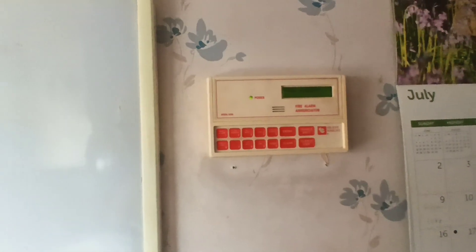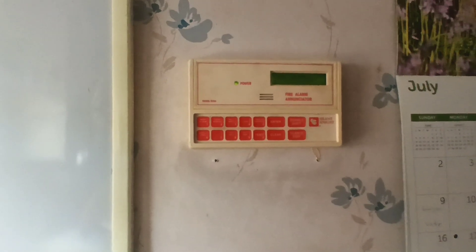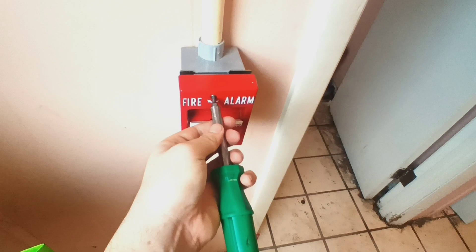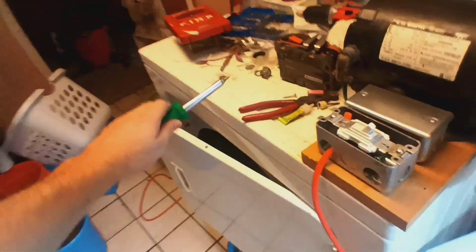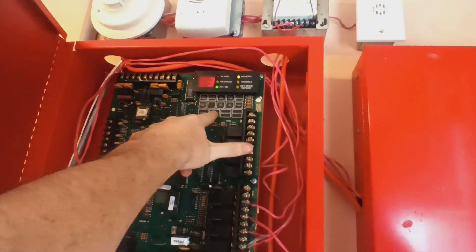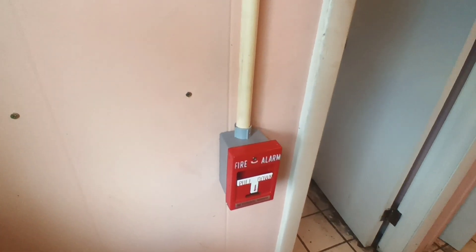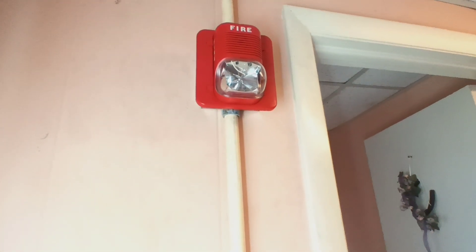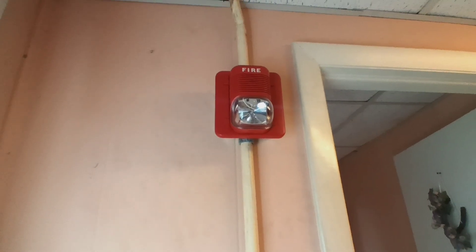Okay, so apparently the Classic SpectrAlert does not like the Simplex Sync Module. I thought it would catch up but I guess it didn't. So I'll reset the pull station. There we go. Let's reset the system. So I guess don't hook a SpectrAlert Classic to a Simplex Sync Module because you'll get these results. That'll do it for system test 11, so thanks for watching and happy 4th of July.